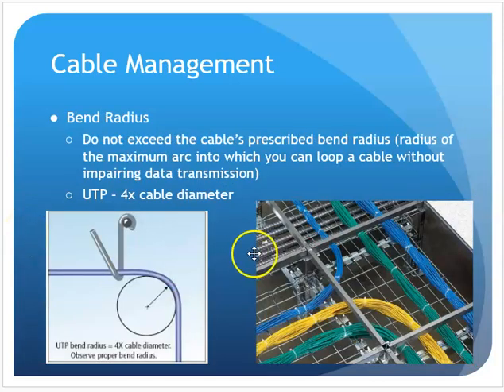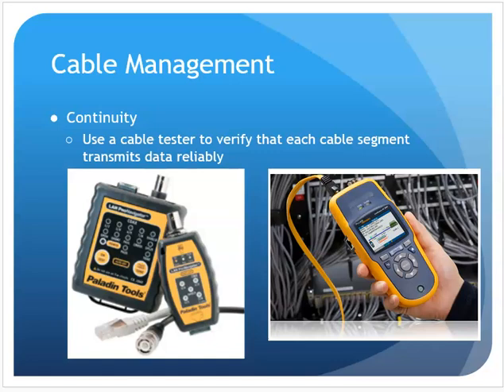When I'm routing my cable, I need to make sure I use nice gentle bends around corners. Sharp bends can cause my cable to not perform at the best level. I might actually have some signal loss if I have a tight bend there. And they call for 4 times the cable diameter as my bend radius. And as you see here, we're doing nice gentle bend radiuses.